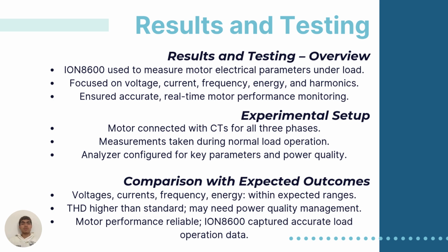Results and testing overview. One, ION 8600 used to measure motor electrical parameters under load. So we have connected the power analyzer into the load just to see how it behaves during operation. And yep, we've got our expected values except the THD.